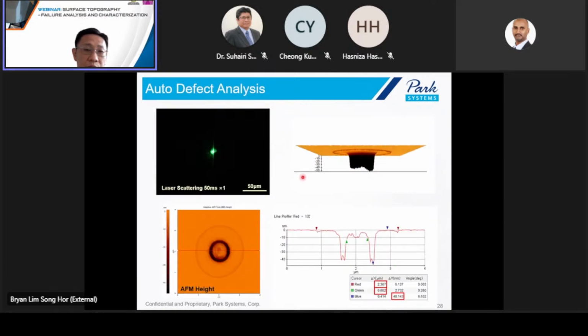So we also have automated AFM tools for this auto defect analysis, where they shine a laser on the area, and if there's a defect, it will reflect up as light, as a bright area, and the AFM head will go there to scan the area and capture the defect information. So we can capture information like the defect height, depth, or the width of the defect.